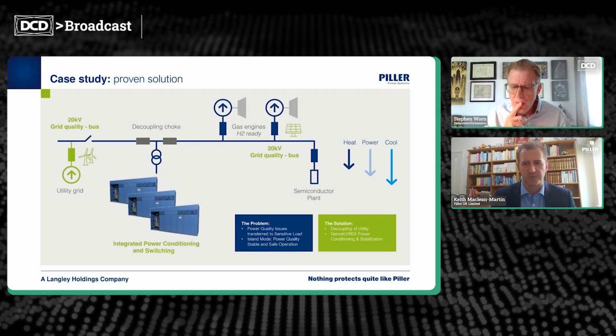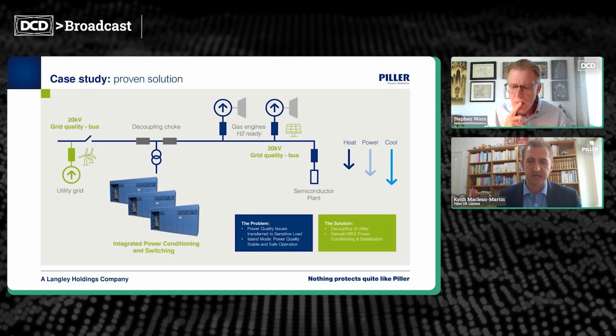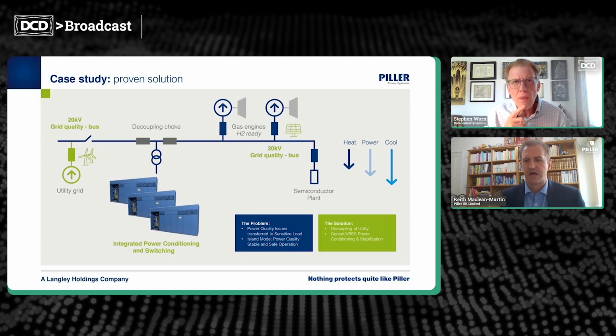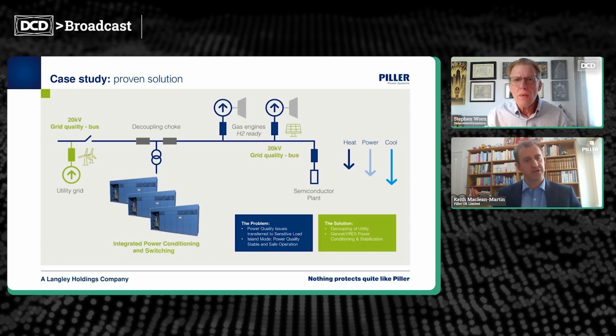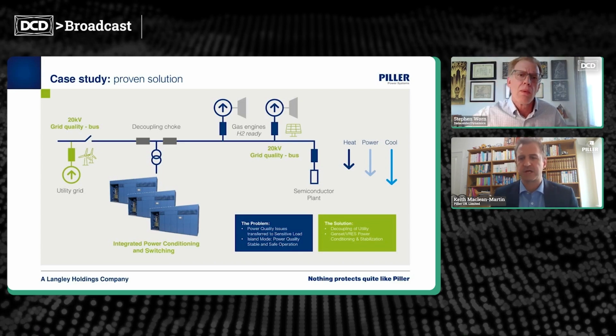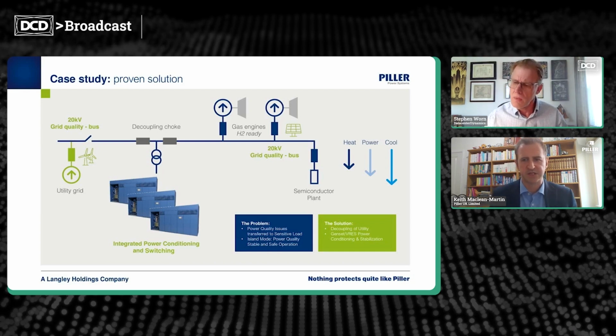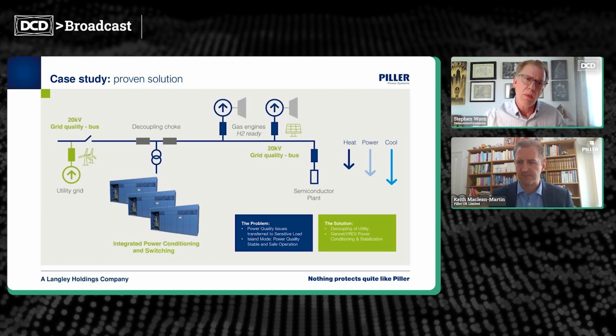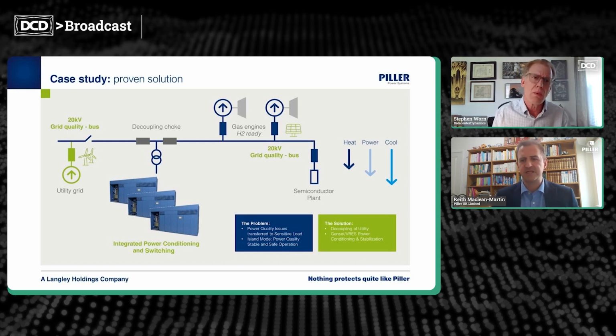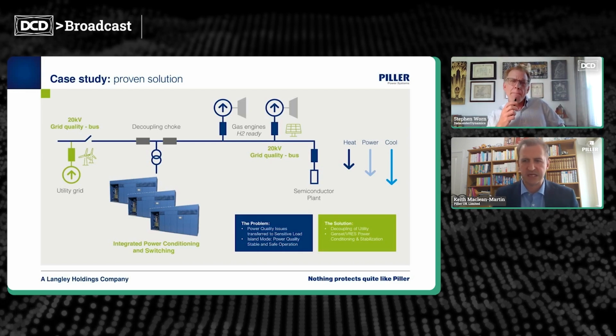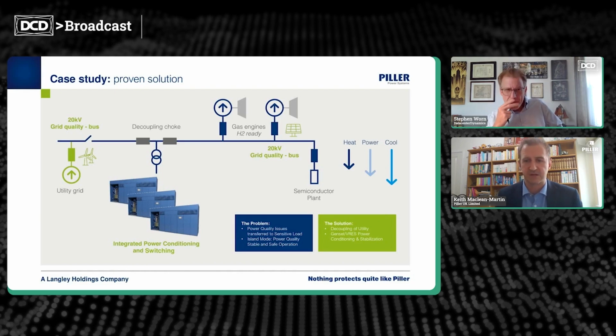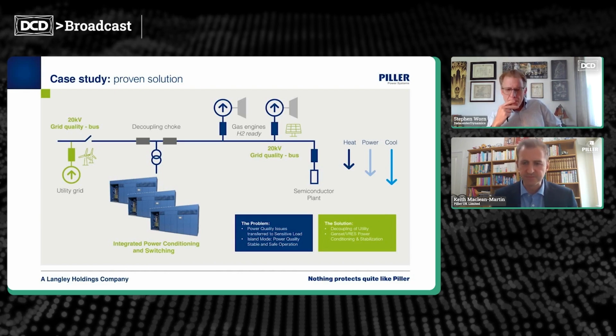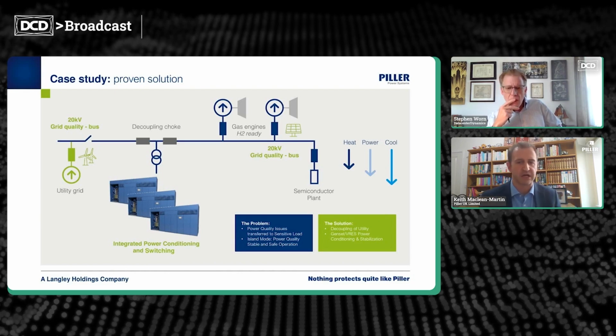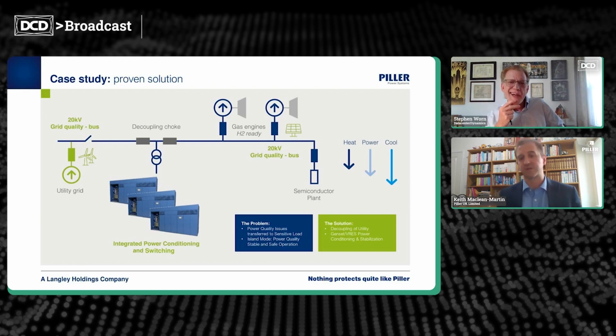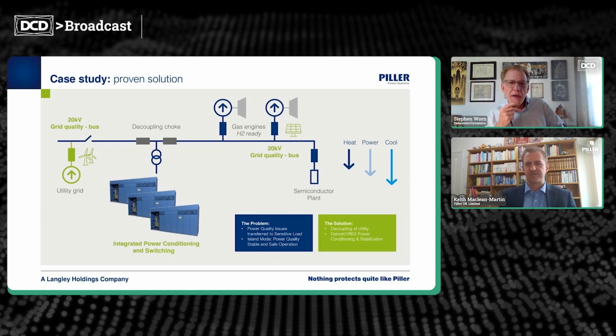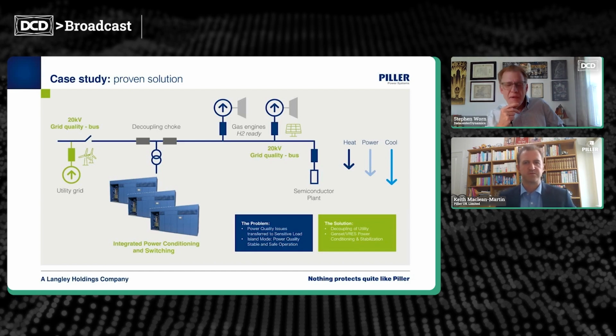Similarly, in island mode operation, the gas gensets were very unstable, again transmitting poor quality to the sensitive loads. The solution we deployed here was to couple an integrated power conditioning and switching technology between the grid and the on-site generation. This prevented the passage of poor quality issues between the grid and the critical loads on site. Effectively, this creates a microgrid connected to a conventional grid quality bus with its own localized, very high quality bus to deliver pure high quality power.